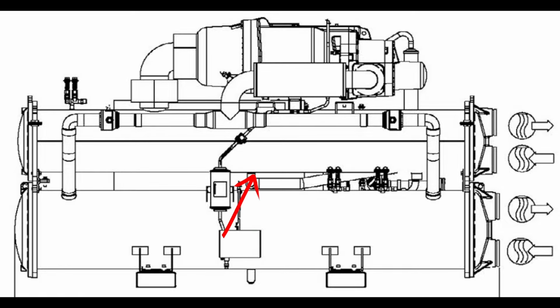Now, for right there, I know that this is a flooded style evaporator because the pipe is connecting into the bottom, and it will fill the bottom through a distribution rail inside the evaporator, and then we'll maintain a liquid refrigerant level above the tubes.